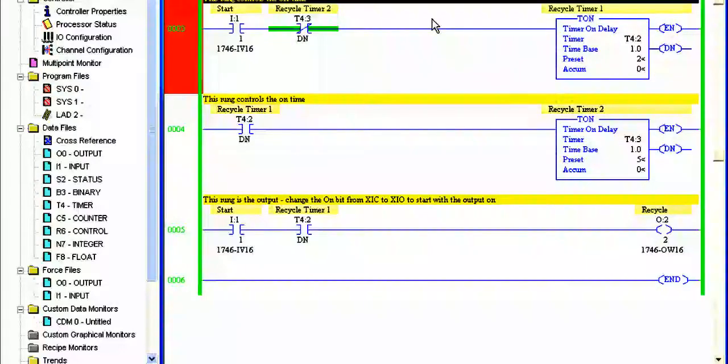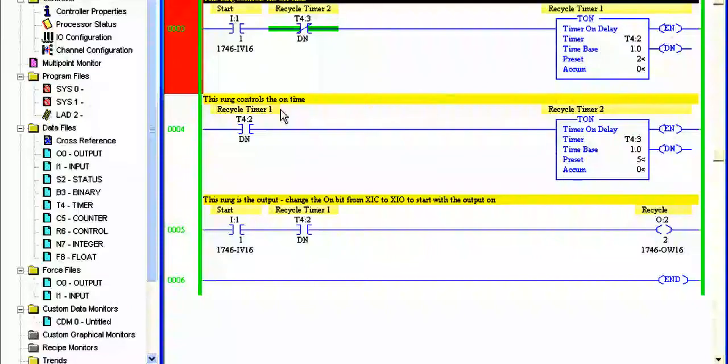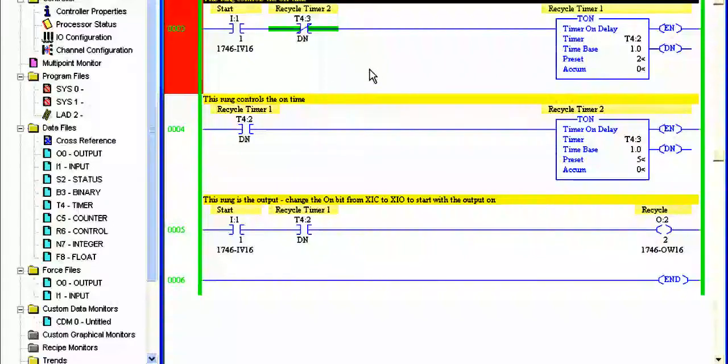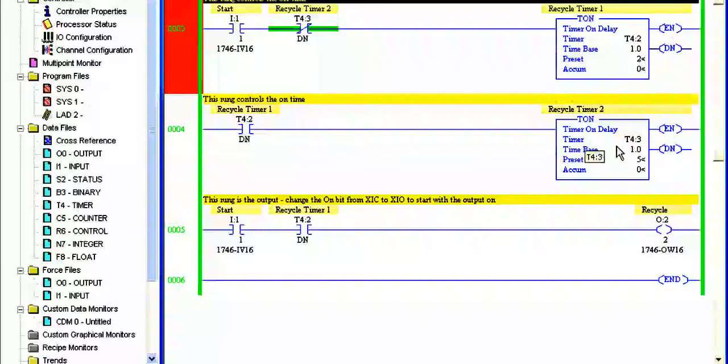In this part of the derived timers we've got the recycle timer and that requires two timers to be included in the circuit. And you'll notice here that the done bit of timer 3 is in the actuation rung for timer 2, and the done bit for timer 2 is in the actuation rung for timer 3. So they're controlling each other. That's why sometimes you'll hear them called cross-coupled. I've got a start bit here that'll turn the whole thing on and these timers will do their thing. I've set one at two seconds, one at five seconds. You can have those settings the same or you can have them set differently. I've also got a bit of the start button here in case I want this output to be on when the time period starts.